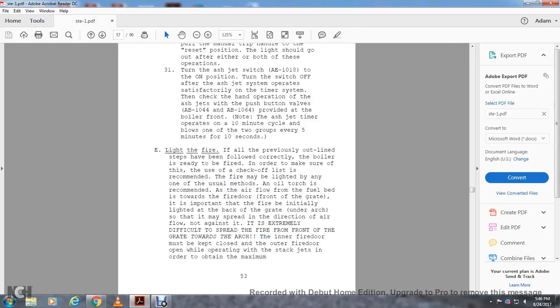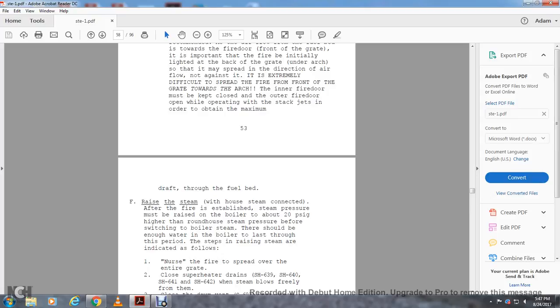Light the fire. If all previously outlined steps have been completed correctly, the boiler is ready to be fired. A checkoff list is recommended. The fire may be lighted by any one of several methods using oil torches. The recommended method uses an oil torch. The airflow through the fuel bed is from the fire door at the front of the grate. It is important that the fire be initially lighted at the back of the grate, under the arch, so that it spreads in the direction of the airflow, not against it. It is extremely difficult to spread the fire from the front of the grate towards the arch. The inner fire door must be kept closed, with the outer fire door open, operating with the stack jets, in order to obtain maximum draft through the fuel bed.